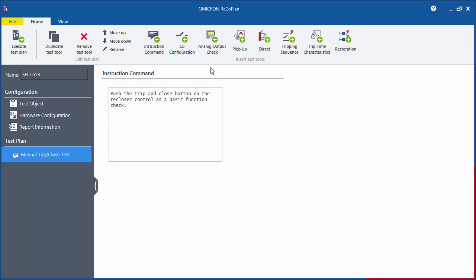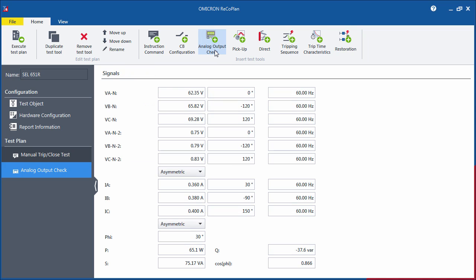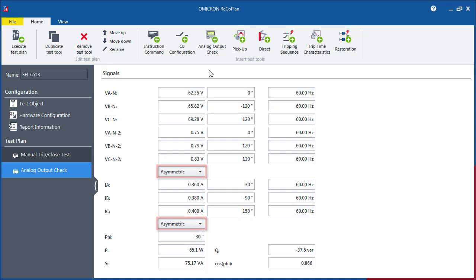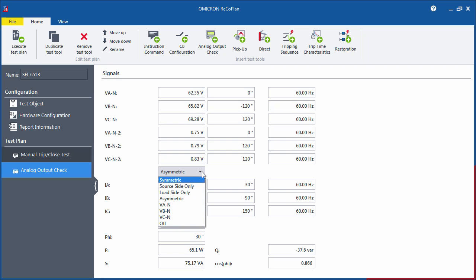The Analog Output Check tool can be used as a wiring check. The default value setting for voltages and currents is unsymmetrical, so you can check the magnitudes from the metering function of the recloser control. You can select a different output mode from the drop-down menu, like symmetric distribution or only one phase output.